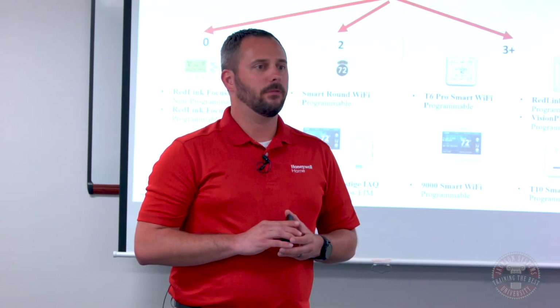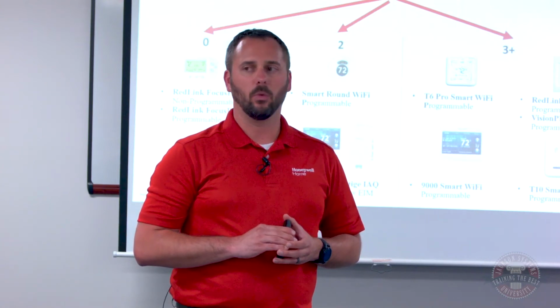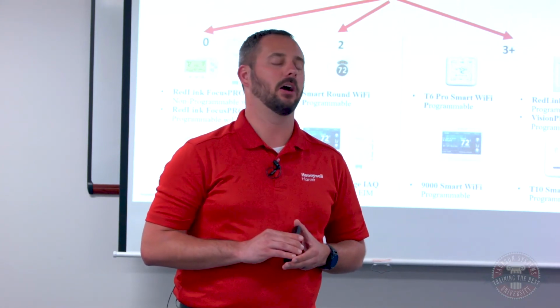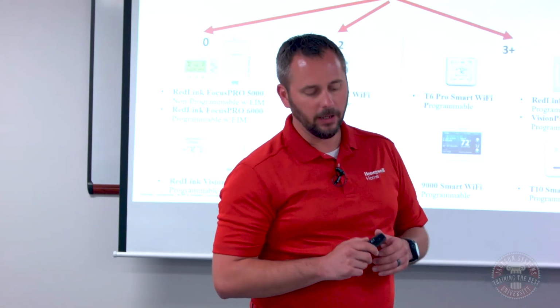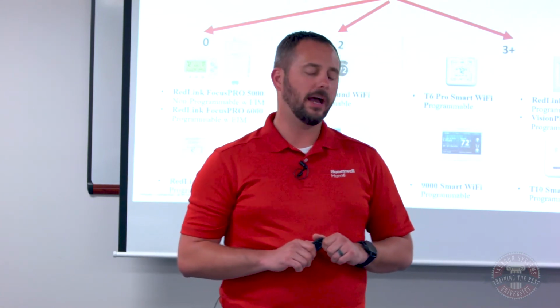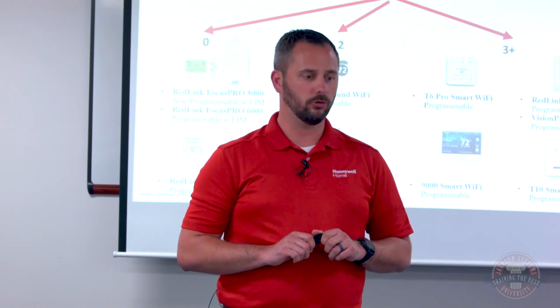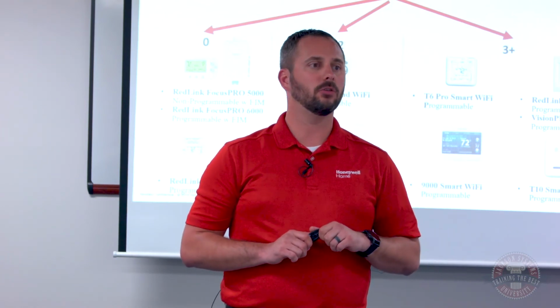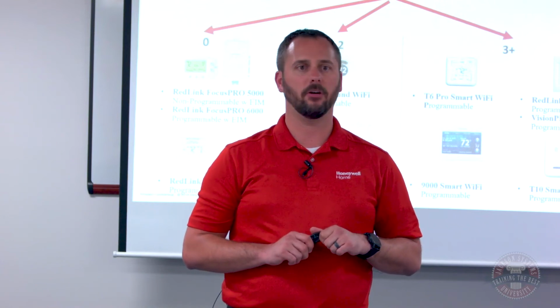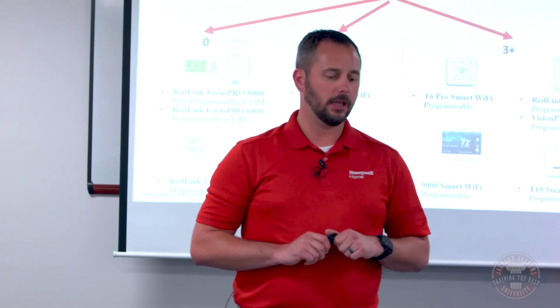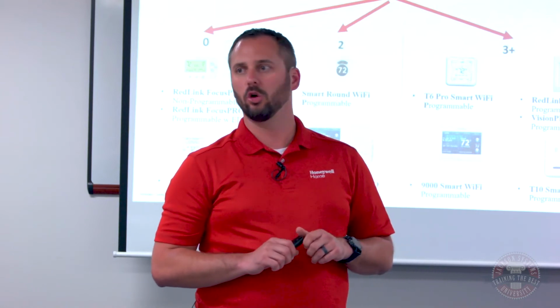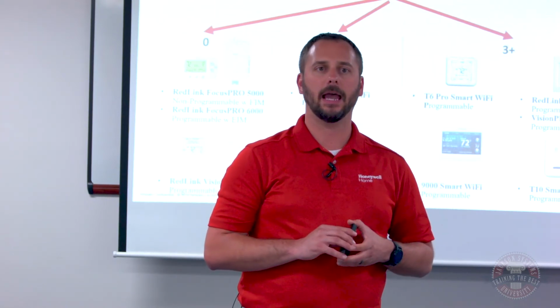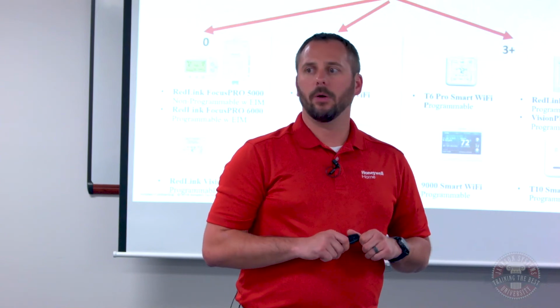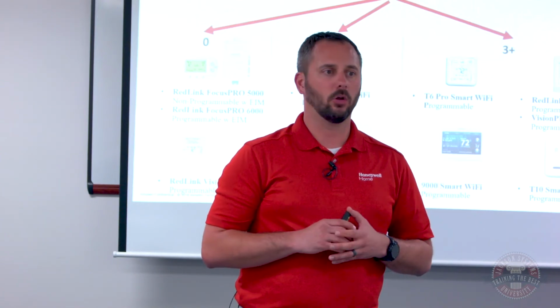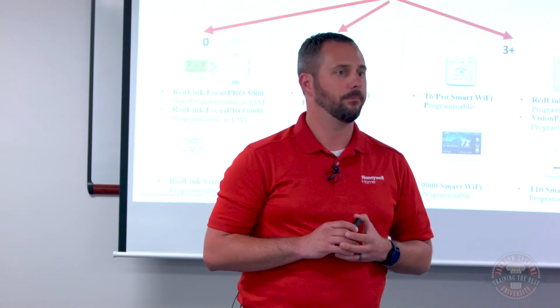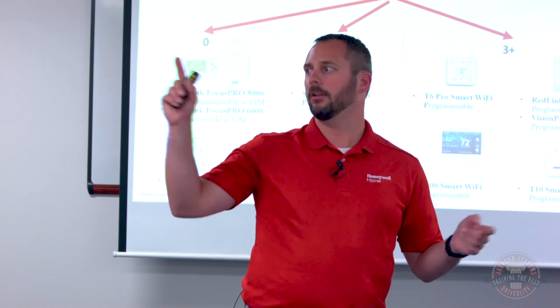It happens if somebody ran 2-strand wire and one of the wires breaks, it could be a rat chewing on it. I mean, I've heard all different types of things. But if you don't have wires in the wall, we do have some options for completely wireless solutions. What you do is you have to use our RedLink products, which is a proprietary wireless communication, and you put a thermostat out in the house or the room, and you put the equipment interface module back at the boiler. The equipment interface module is really nothing more than a glorified back of the thermostat. So it's wirelessly talking to the back of the thermostat.